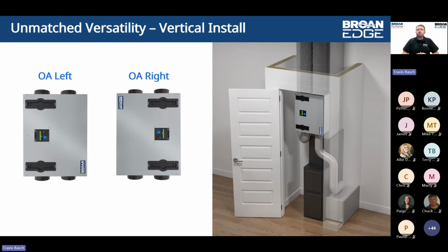You do have the ability to mount this new Edge platform in that vertical orientation, whether that's mounting it directly to the supply plenum, as an example, or additional structure within that mechanical closet. That is a very nice means of getting a nice tight packaged mechanical closet while still providing easy access to the ERV, again, whether it's for service or maintenance or just general commissioning and install.